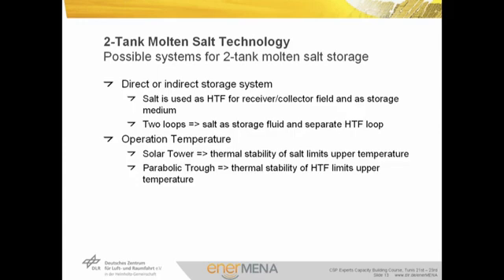In indirect storage systems, two separate loops are used, and the heat transfer fluid in the absorbers is different from the molten salt used in the storage system. The decision between direct and indirect systems depends on the operation temperature of the CSP facility. In today's parabolic trough systems, thermal oil is used in the absorbers, so two separate loops are used. In central receivers, molten salt is also used as HTF in the receiver, so direct storage can be applied.